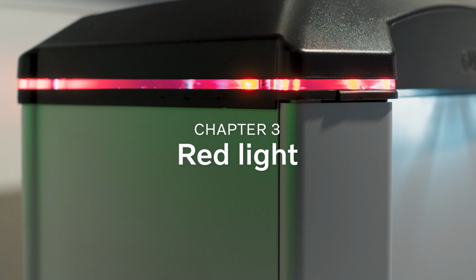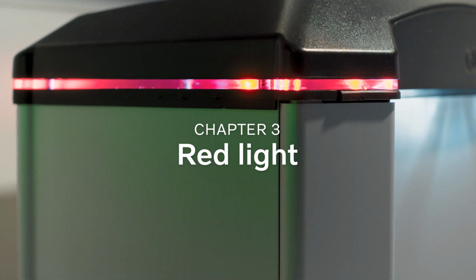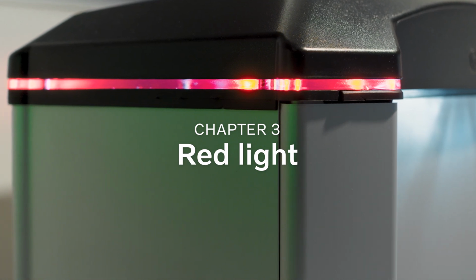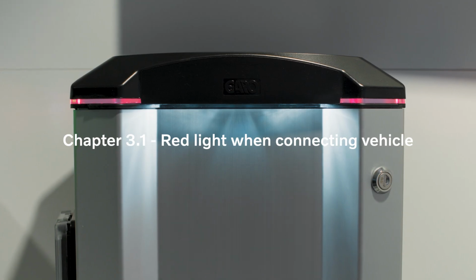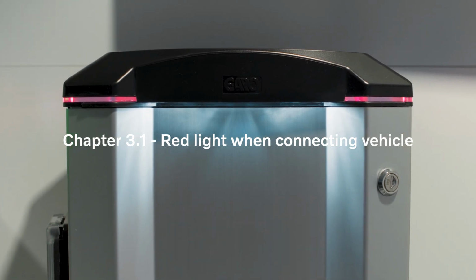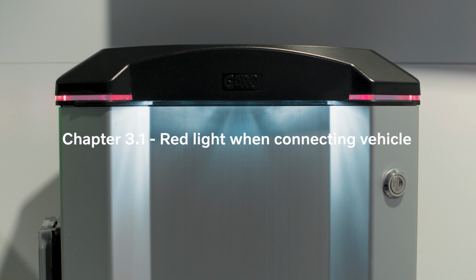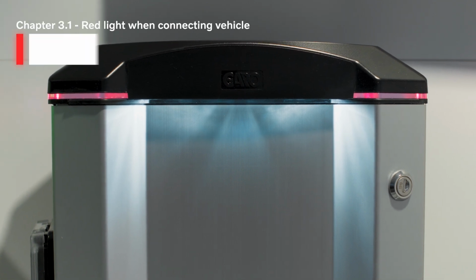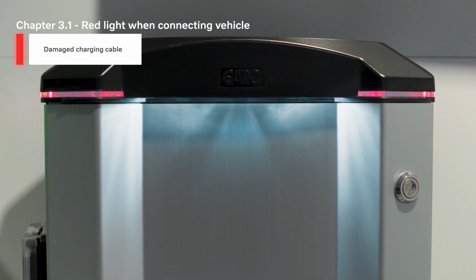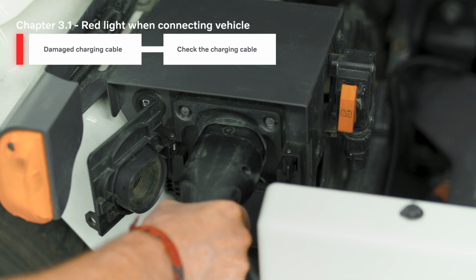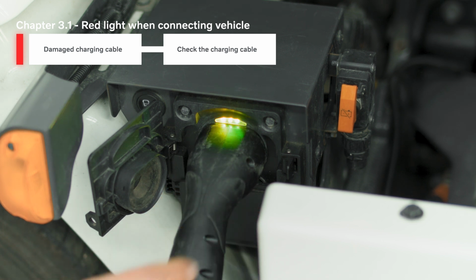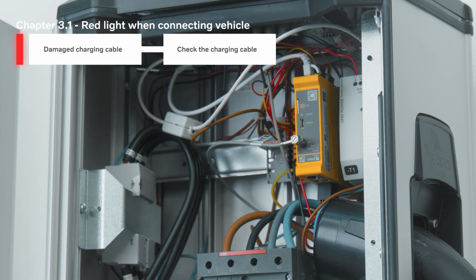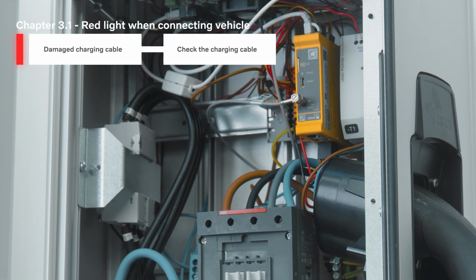Red light indicates error. By following these steps, you might detect what causes the error and how to solve it. If a firm red light is displayed when you connect the vehicle, this might indicate that the charging cable is damaged. Check the charging cable and the connectors for damages, and verify that the CP connection pin and the red wire isn't loose, or that the connections are bad in either of the ends, including inside the wall box. You should also verify grounding of the charging station.